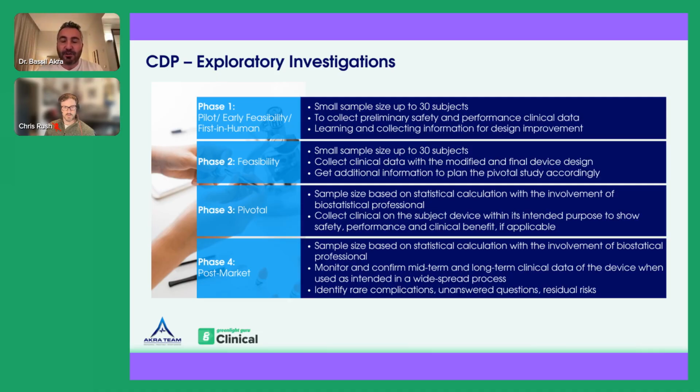During that clinical evaluation process, you need to define what kind of data will close the gap before you re-evaluate the data and build the conclusion that that device is safe and performing well. And the clinical evidence package is never only the pre-market evidence. It's a combination of pre-market data and post-market data. And just that storyline would allow you to tell a notified body or an authority that your device has enough evidence to support safety, performance, and the clinical benefit claim that you have.